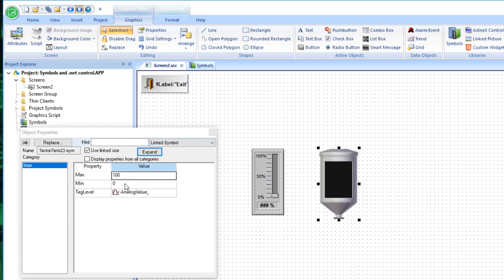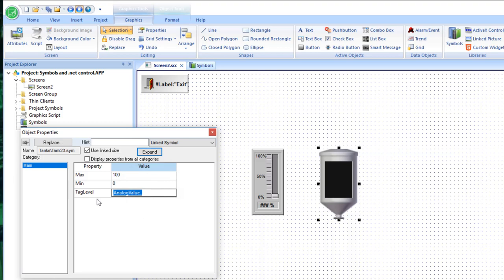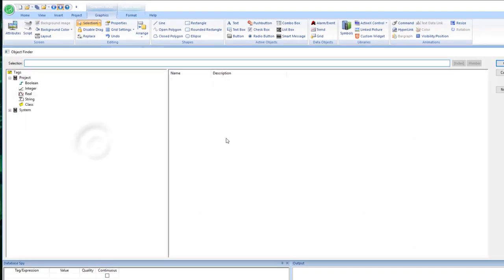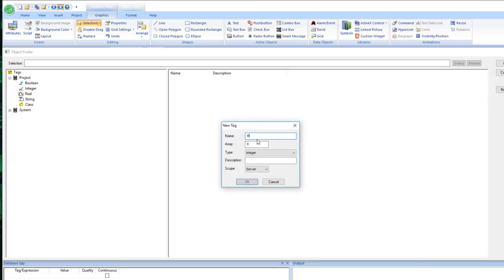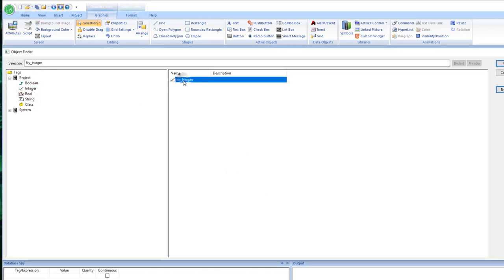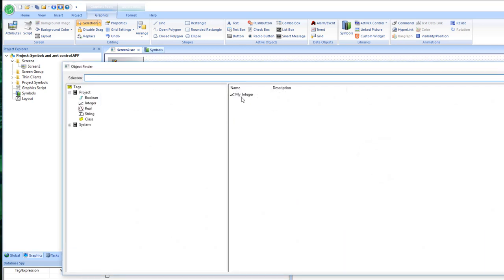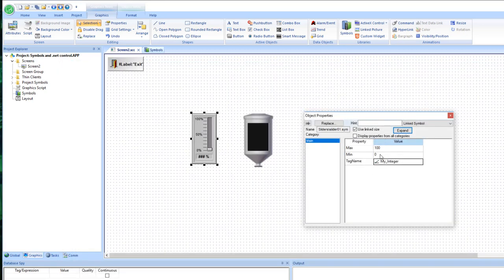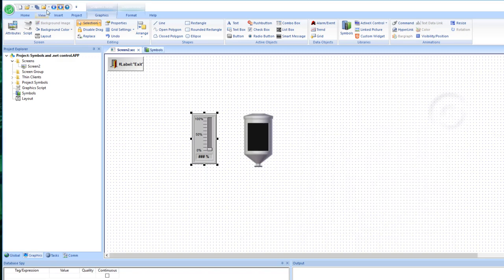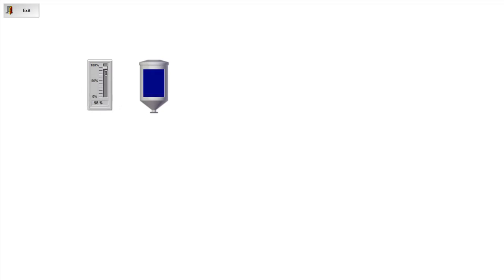You can put a tag name or a hard value in those properties. I'm going to change the tank level tag — I'll create a new tag called my_integer. I'll assign that same tag to the slider as well, keeping the 0 to 100 range as default. If I save the screen and start the application, I can drag the slider bar up and see the tank value go up, and drag it down to see it go down.